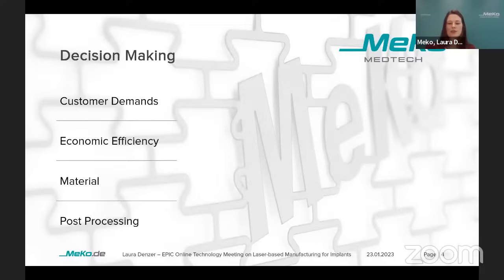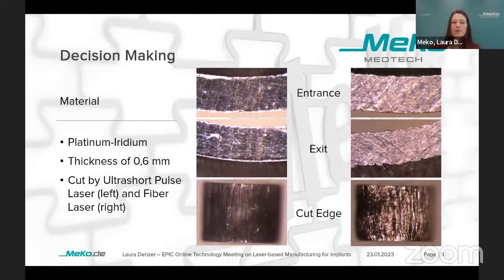I will give you an example for this. Here we cut some platinum iridium. Both sides are the same thickness, 0.6 millimeters. But the left-hand side is cut by an ultra short pulse laser and the right-hand side is cut by a fiber laser. We tried out where we should cut this, also in terms of efficiency, for example. It's the same component we cut. But as you can see on the left-hand side, the cut edges are way cleaner than on the right-hand side. On the right-hand side, we tried to do it as fast as possible. On the left-hand side, it was more to be precise and to really have a good cut edge.